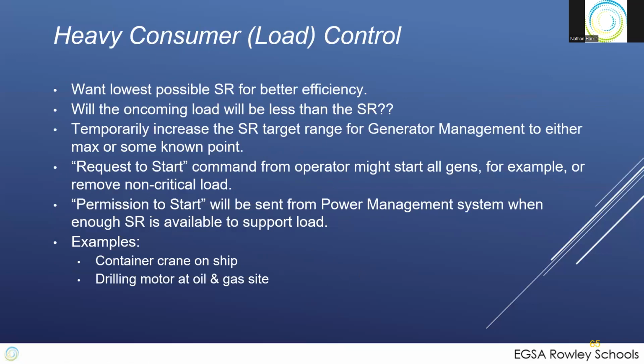Heavy consumer control. In this case, you're trying to reduce SR to the lowest possible. Let's take, for example, a drilling motor at an oil and gas exploration site. You've got a small generator that feeds the air conditioner and the control trailer, giving them control power, living quarters, that kind of thing. Maybe a 20 or 50 kW generator does all the auxiliary equipment. When it's time to run that big drill motor, it won't run off that little generator. So you start up the big generator, and you run your drill off that. So heavy consumer control is increasing the spinning reserve.